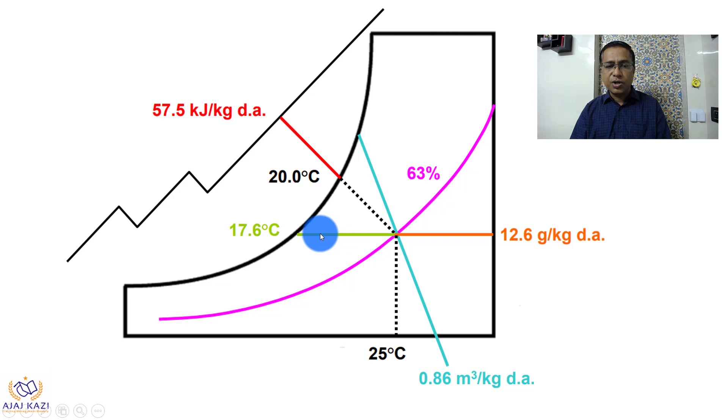This line which goes over here gives me a dew point of 17.6°C. The right-hand side gives me the humidity ratio. The purple line which comes from this point gives me the RH, the relative humidity of 63%.